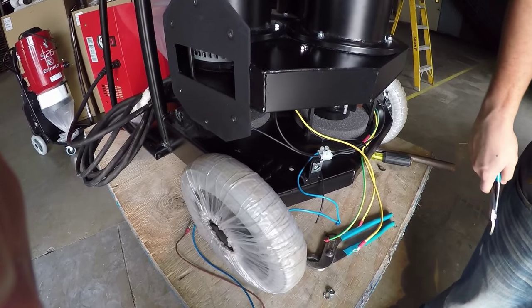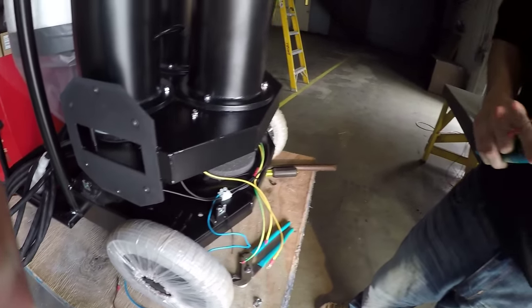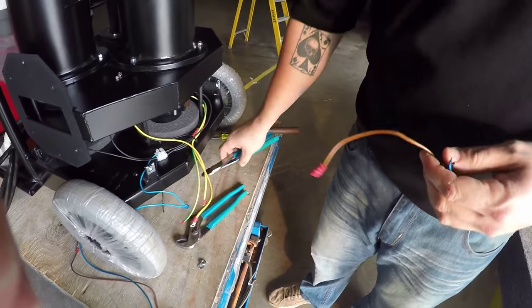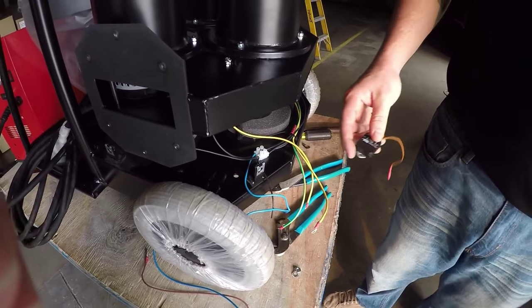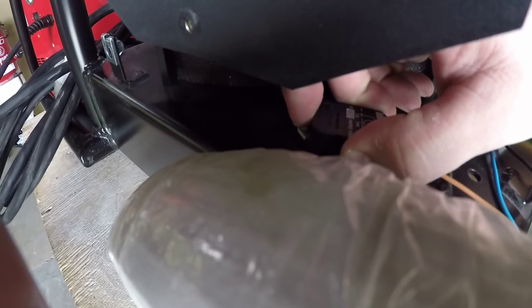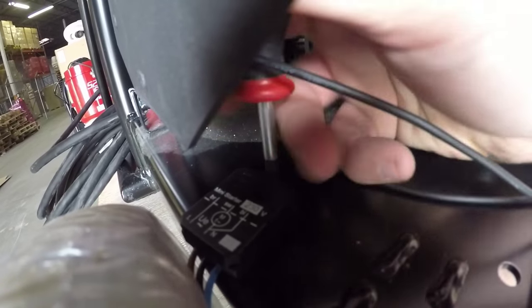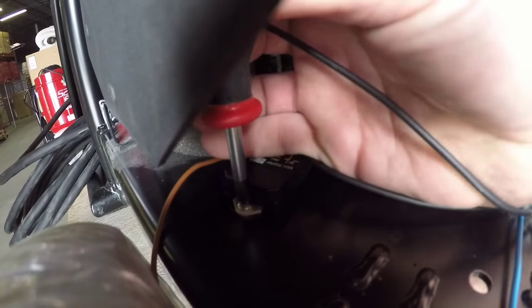Now we're going to reinstall the electronical filter and the soft start. I have pre-cut the wires to go back in accordance and crimped on a new quick-connect terminal. The soft start comes with a rivet, but when you're in the field and don't have a rivet gun, it can be easily placed back in with a screw and a locking nut. You will also need a very small Phillips to get inside here. Now you're ready to crimp your wires back.